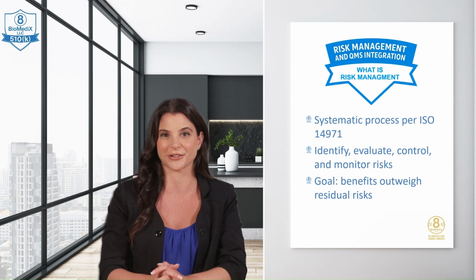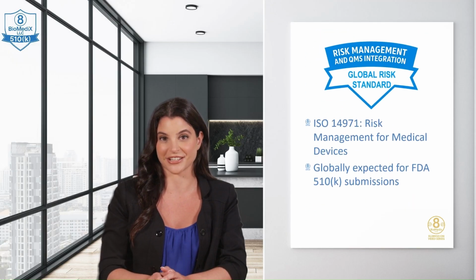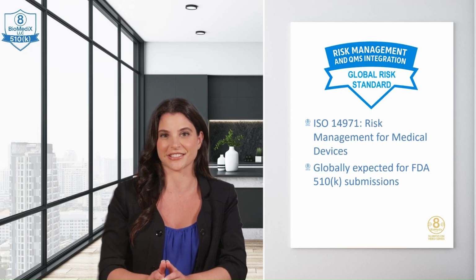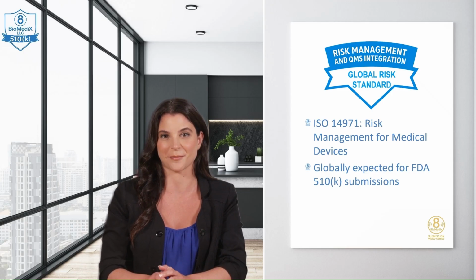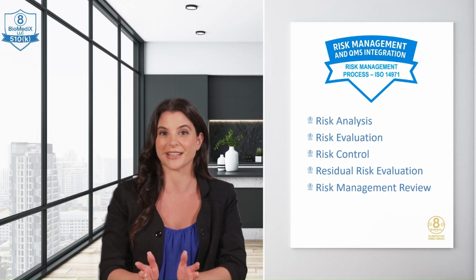Its ultimate goal is to ensure that the benefits of using your device outweigh the residual risks and that these risks are acceptable. The international standard that guides this process is ISO 14971, Application of Risk Management to Medical Devices. This standard outlines a comprehensive framework, and adhering to it is a fundamental expectation for regulatory submissions globally, including FDA 510(k)s.